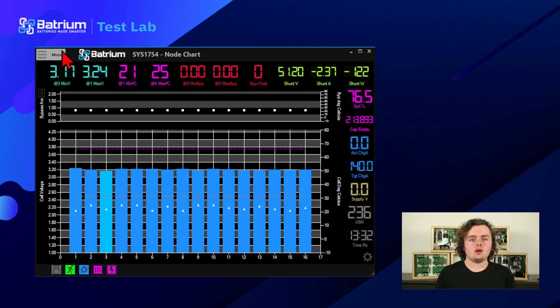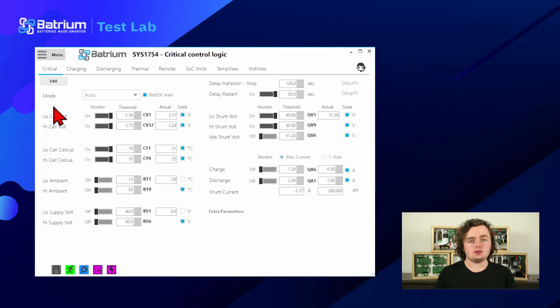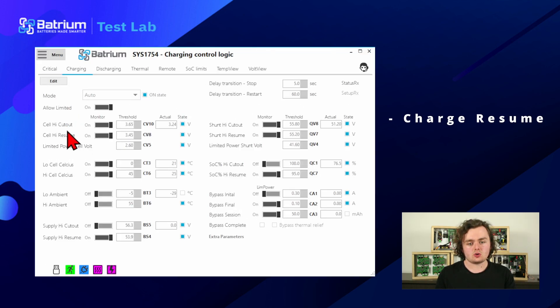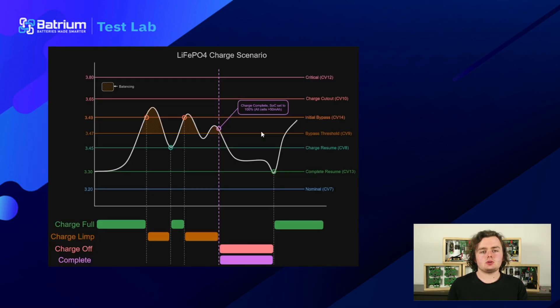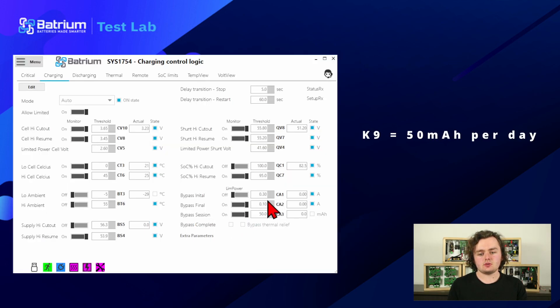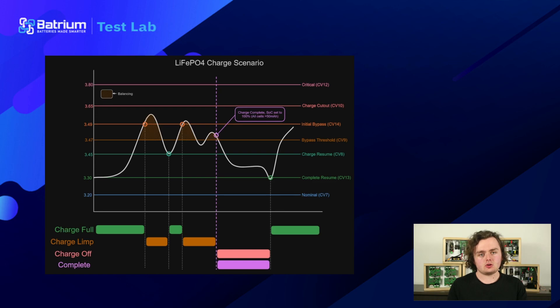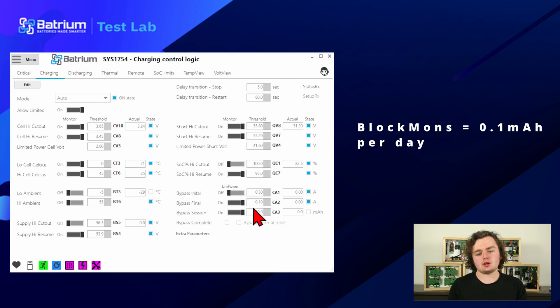We've slowed down, voltages are coming down, and the charge stays slow until we hit the charge resume threshold. Bypass complete is reached when we've done enough accumulated balancing on all cells — that's 50 milliamp hours, which you can configure, and that's per day or per cycle. For block mons, if all cell monitors have hit 0.1 milliamp hours at some point in the day, that counts too.